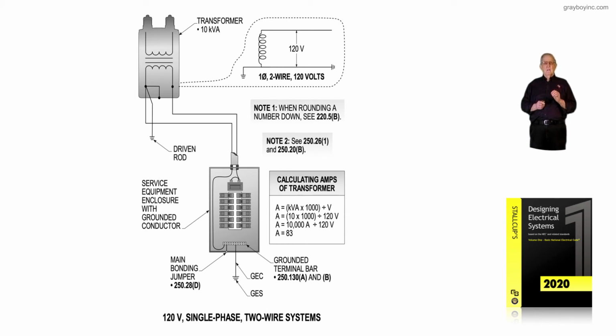And then, of course, the grounded conductor shown coming and terminating to that grounded terminal bar would also be sized from Table 250.102(C)(1) to carry the fault current if such a condition develops somewhere in the system. But you would also design that conductor based upon neutral current from 220.61 and select the larger, either the larger calculation of 220.61 as a neutral, or a path for the fault current to travel over per Table 250.102(C)(1). That's just a little extra information.